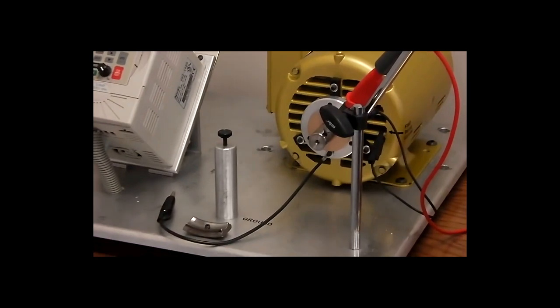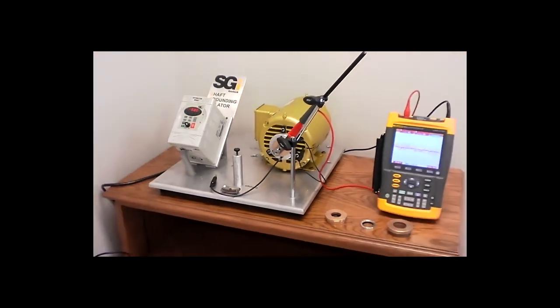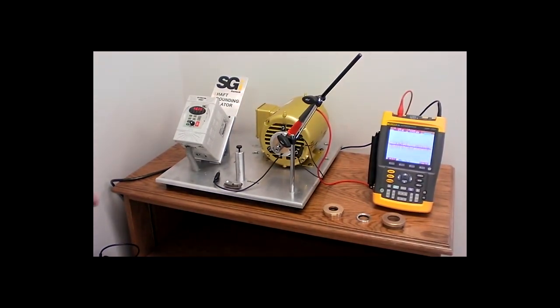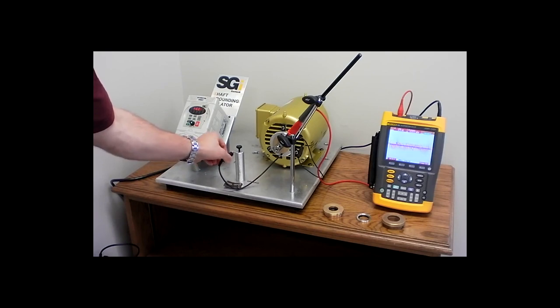This voltage can range anywhere from 10 to 40 volts. Once the SGI is activated, providing a path of least resistance to ground, it can be seen on the oscilloscope that the voltage essentially zeroes out.